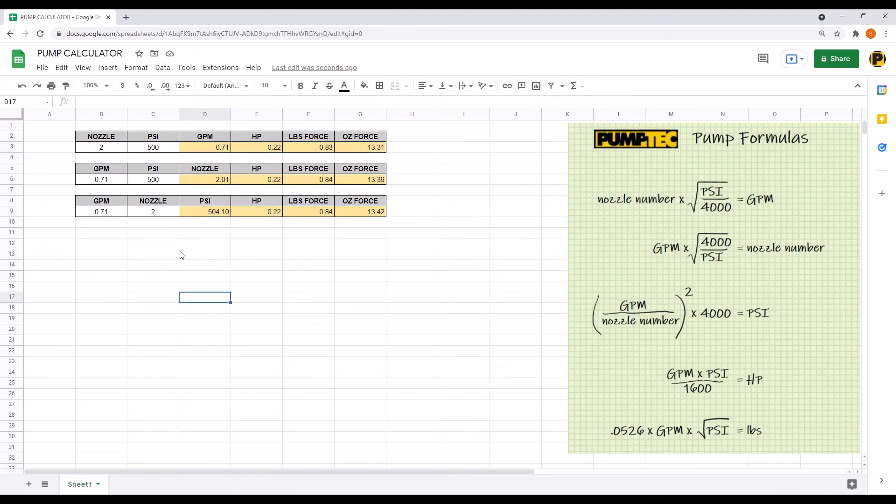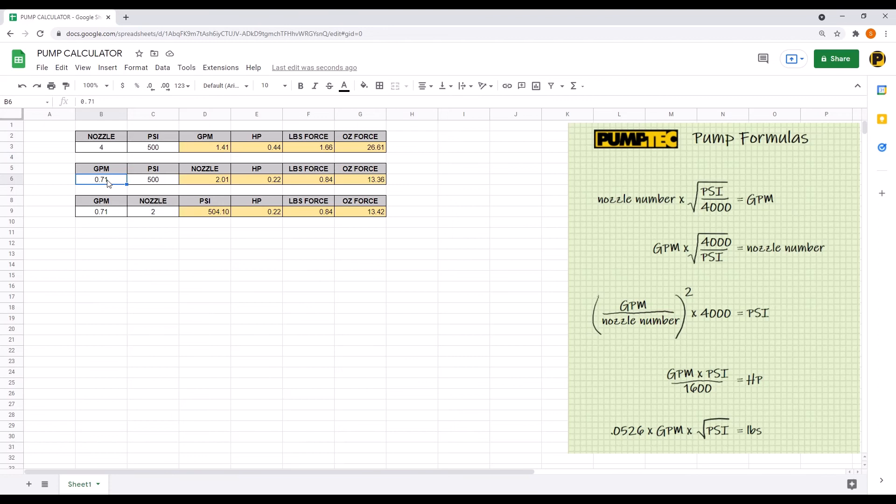Now you can change the inputs to see how they affect the outputs. So if you put a number four nozzle at 500 PSI, it requires 1.41 GPM.